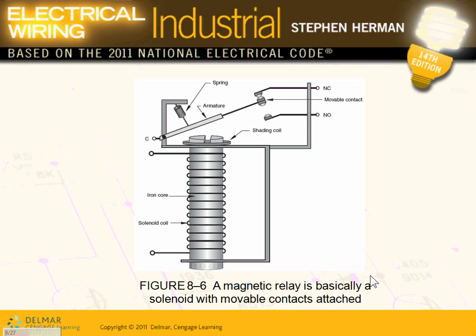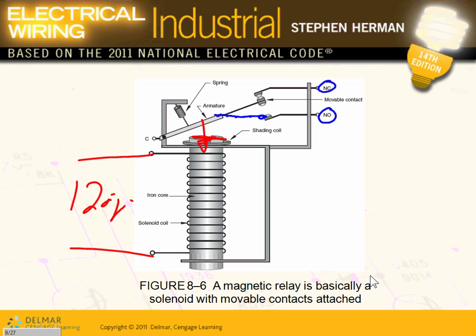Magnetic relays or magnetic starters: you bring a voltage — 120 volts — create a magnetic force that physically and mechanically pushes these contacts. When you grab this contact, this is normally closed and this is normally open. What happens when you energize it? The contact will change position — from normally closed to normally open.